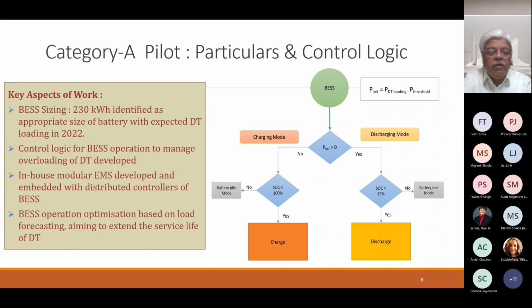On the right hand limb, when we supply through these battery systems, we check the state of charge available in the batteries. When it is greater than 15%, the logic allows discharge or supply through the batteries. If it is less than 15%, the battery remains in idle mode.